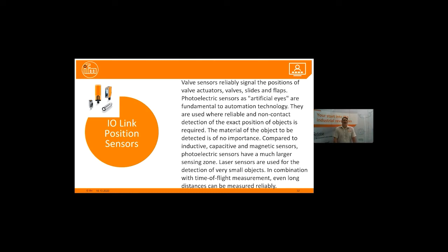Photoelectric sensors are artificial eyes and fundamental to automation technology. They are used where reliable and non-contact detection of the exact position of an object is required. The material of the object to be detected is of no importance. Compared to inductive, capacitive, and magnetic sensors, photoelectric sensors have a much larger sensing zone. Laser sensors are used for the detection of very small objects. In combination with time of flight measurement, even long distances can be measured reliably.